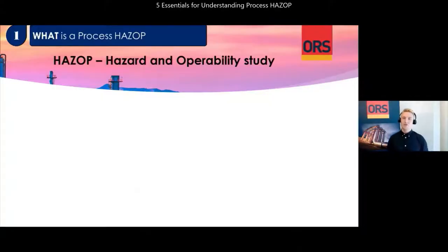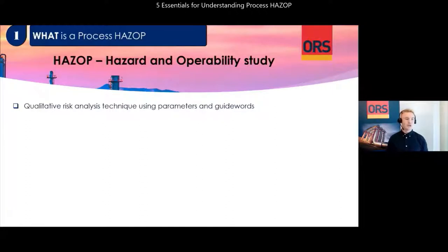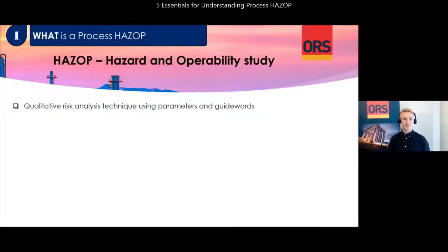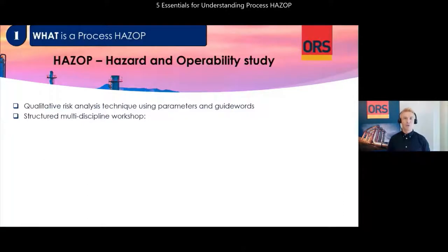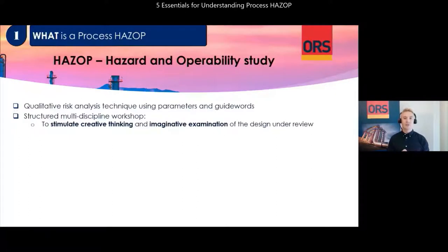We will start with: what is a HAZOP? HAZOP is short for Hazard and Operability Study. A HAZOP is a qualitative technique based on a combination of parameters and guide words to produce a deviation from the design intent or intended operational mode. The HAZOP is conducted in a multi-discipline workshop with participants from relevant disciplines, to stimulate creative thinking and imaginative examination of the design under review to ensure that various viewpoints are expressed.